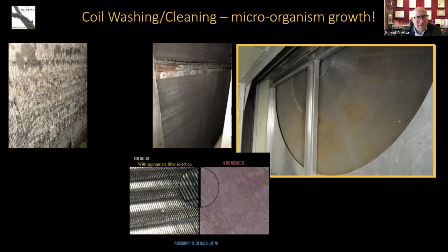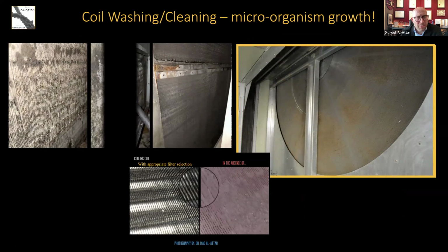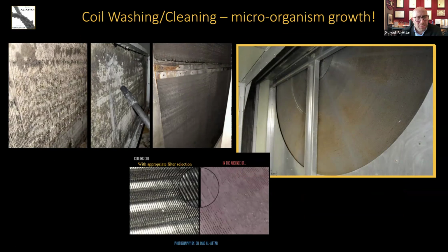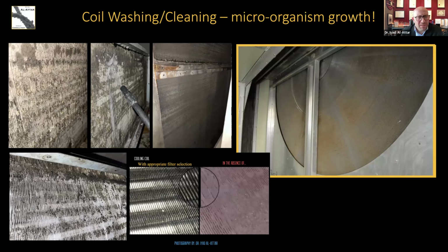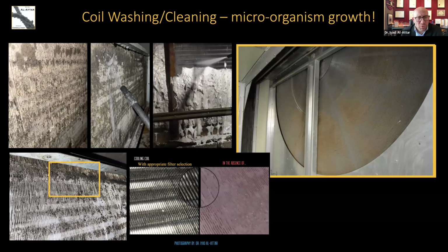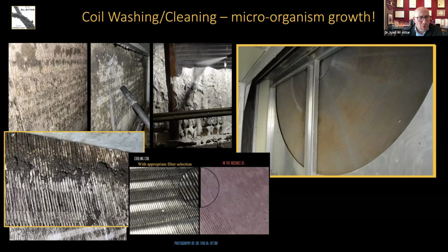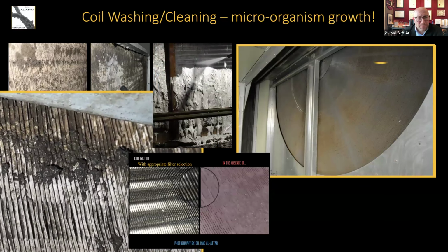What I'm showing you here is contaminated coils, which my colleague, Dr. Engineer Iyad, will address in his presentation. It's very difficult to bring this coil back to the design or original condition so that your heat transfer mechanism is optimized. It gets very difficult because sometimes you're washing dust and water into the coil, rather than out of it.